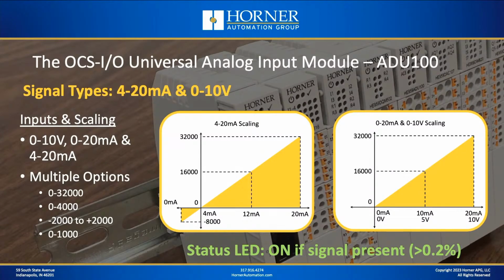Now, if you choose 0 to 10 volts or 0 to 20 milliamps, you don't get quite the resolution with 0 to 20 milliamps, for instance, but you can detect all the way down to 0, with a reading of 0 counts correlating to 0 milliamps or 0 volts, and a reading of 32,000 counts representing 20 milliamps or 10 volts. So if you're talking current, I definitely recommend 4 to 20 milliamp as the range you should select. If you're talking voltage, of course, I still recommend 0 to 32,000 as the range you would select.